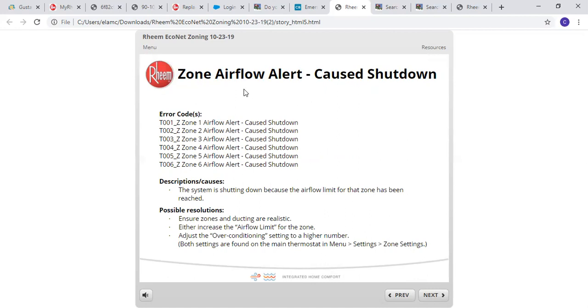This is for your zone airflow alert. It caused the shutdown. So it gives us 6 zones to choose from here. So we'll pick zone 3, T003Z, zone 3, airflow alert, caused shutdown. The description or cause: the system is shutting down because the airflow limit for that zone has not been reached, or has been reached.